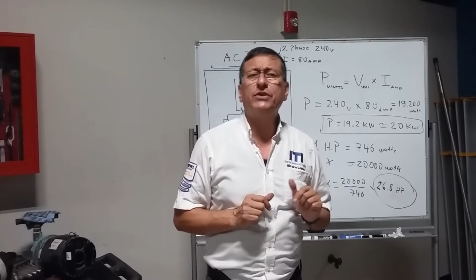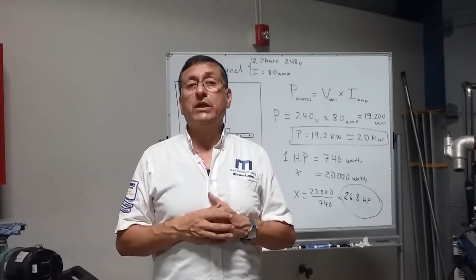Another common question is, my generator is running, however the engine is broken, and I need to replace only the engine. And the $1,000,000 question is, how much should be the capacity of the engine, for example, in this example, in order to repair the 20 kilowatt generator? How much should be the capacity in horsepower of the engine? I want to replace that engine with another engine with the minimum capacity necessary to produce 20 kilowatts.